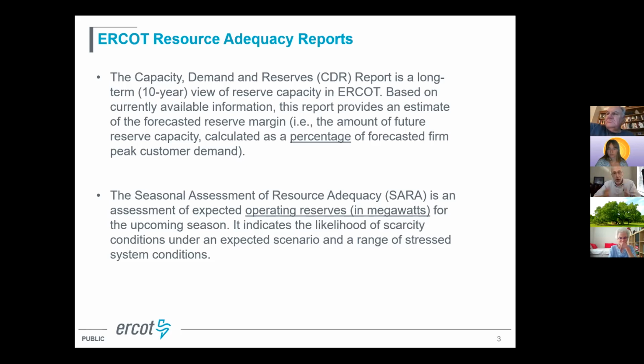So, just as an example, if you had 100,000 megawatts as your expected peak demand, and you had 10,000 megawatts of reserves, 10,000 is 10% of 100,000. So you would say you had a reserve margin of 10%.